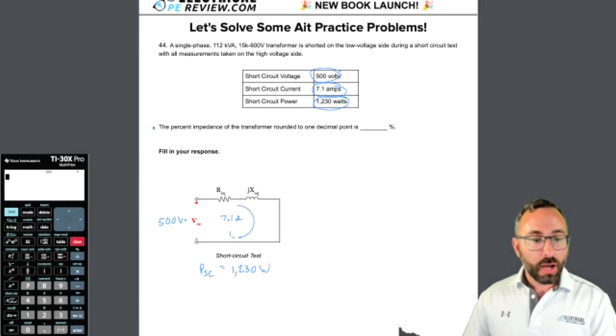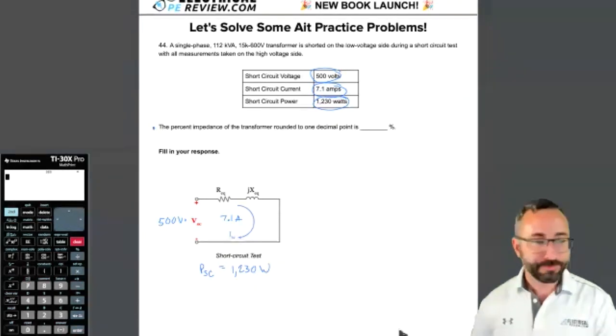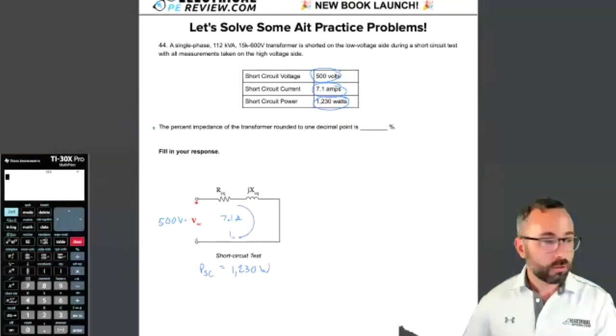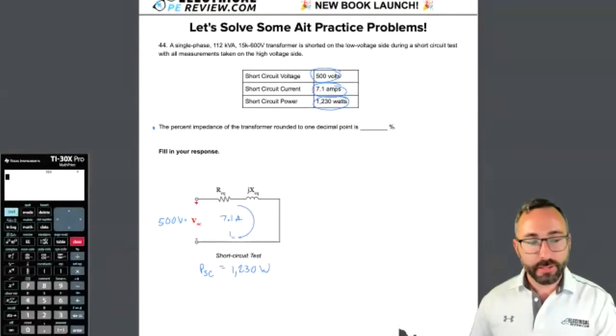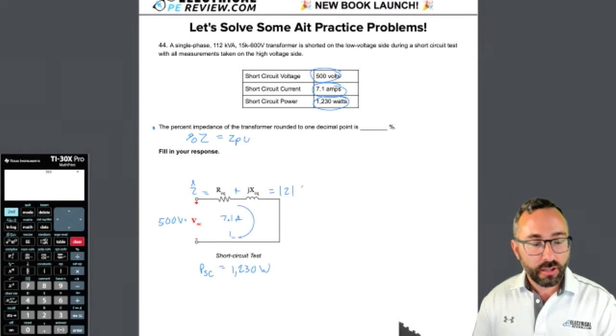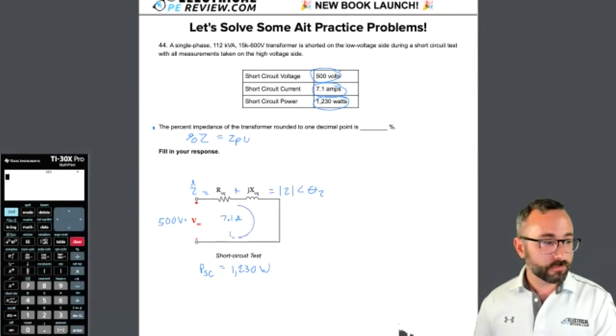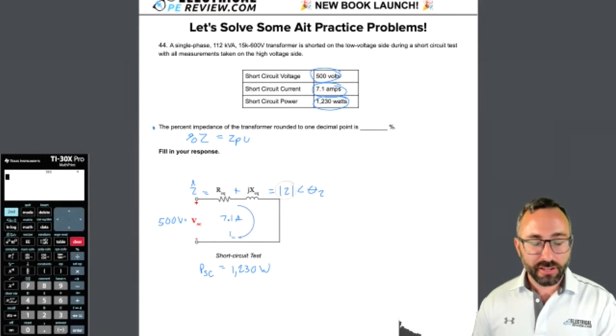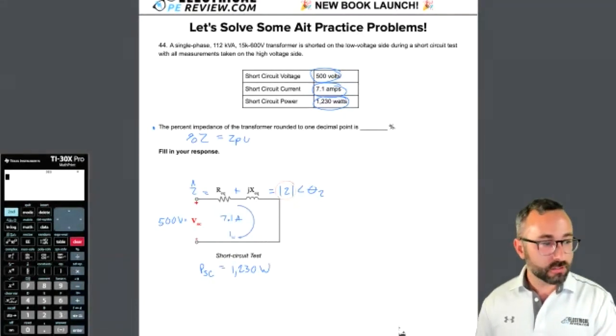All right, so we've got the transformer short circuit test. Step number 1, if I want to find the percent impedance, what is percent impedance? It's really the per unit impedance. Here's my transformer winding impedance. I can say complex Z equals R plus j X_EQ. That's rectangular form. Can I represent this in polar form as magnitude Z angle theta Z? Yeah, sure can. So if I can figure out magnitude Z, I can eventually get to my per unit impedance.